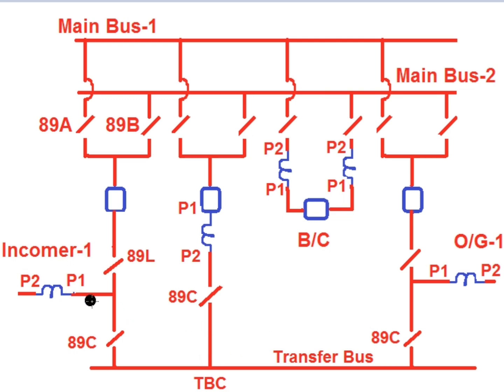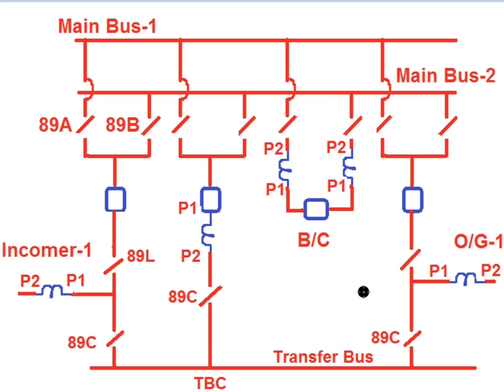Any feeder can be diverted via the TBC bay if maintenance is required for a circuit breaker. Either an incomer or an outgoing feeder can be diverted to the TBC bay. In this video I will discuss bus bar protection of the two main bus and one transfer bus system.